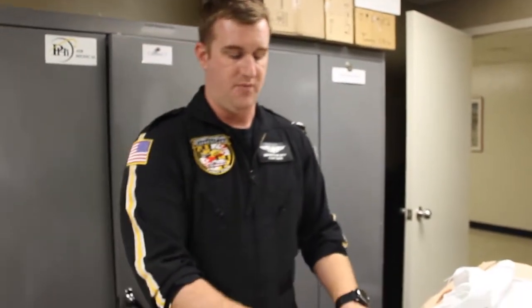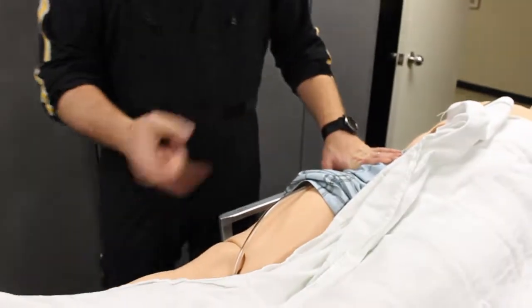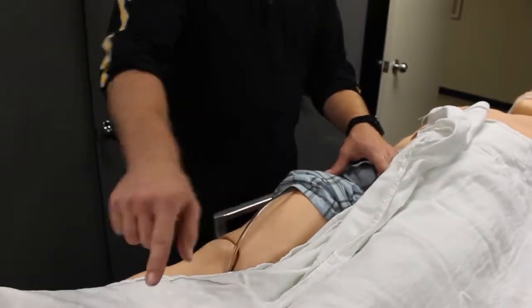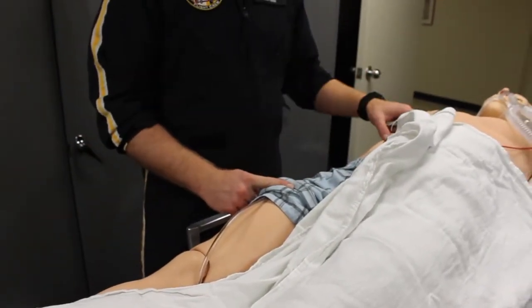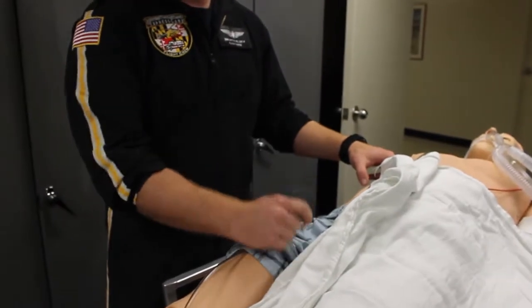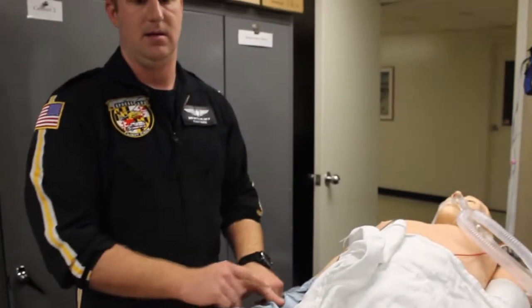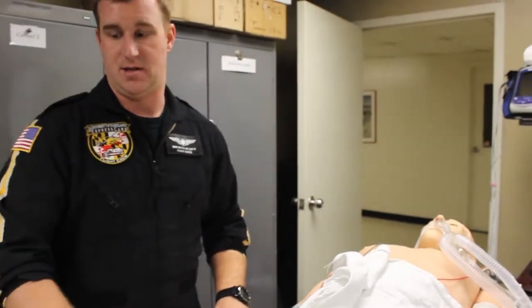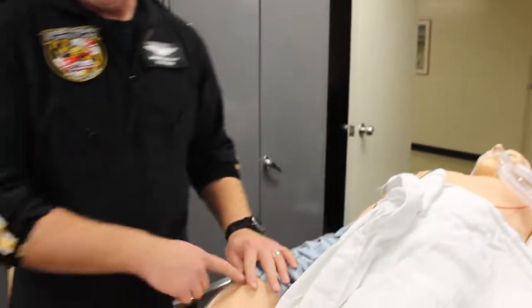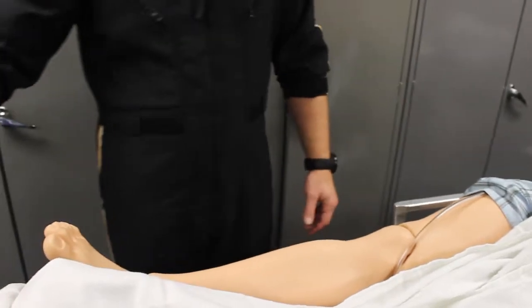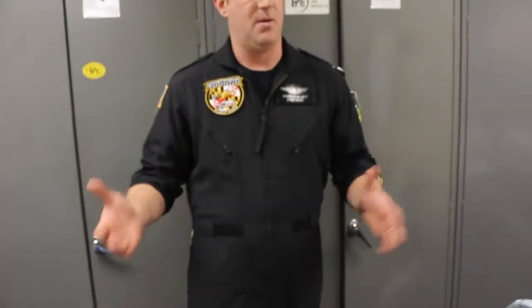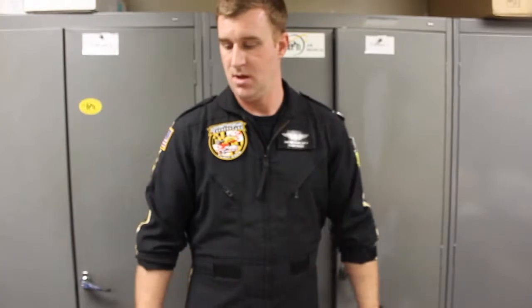They're going to be running through an introducer that's sutured, and then they'll suture the actual balloon pump line in. So you're going to have one drive line coming out that has off the side of it your A-line setup. So you've got your center lumen that's your A-line setup, and it comes off and connects right there at the side. And then you've got your drive line that's coming off. And 95% of the time they're running down the leg and they're at the base of the patient. They're off at their feet. We're going to change it over there, but then we're going to move the balloon pump up off the left shoulder for loading purposes.